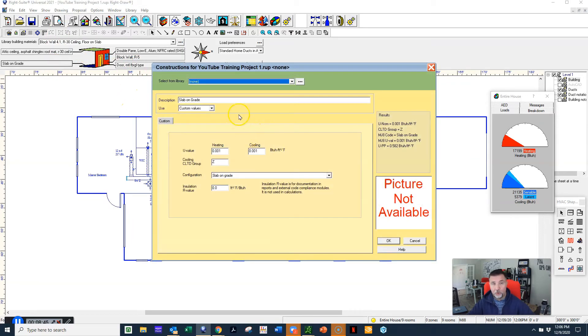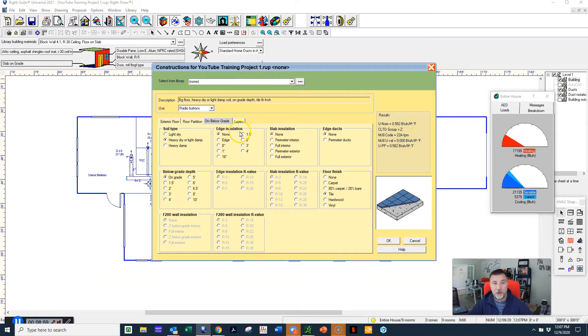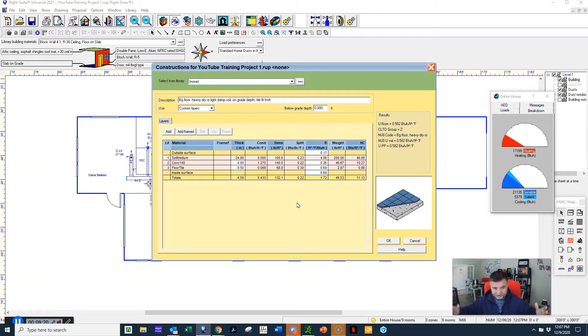You even have your slab on grade. If we're going to have a slab on grade, where are we going to put it? And then what it does is it builds these values. If you actually open up your Manual J code book, it's going to have these specific descriptions to help you out. Here's your slab, here's your soil—the soil on the concrete actually has an R-value, an insulation value. When you're in a northern climate that makes a big difference because the edge of the slab actually will allow cool air to get in, and you need to create an insulator around that. This project happens to be in a southern climate.